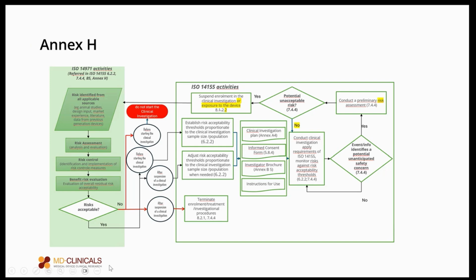It seemed that some confusion was that Annex H had possibly two or several rounds, where if something happens during the clinical investigation that is unanticipated, you need to go back to your risk management from 14971 and consider, and your second round kind of doesn't fit completely in our diagram anymore. So we now have two, and I hope the lines and the colors make it clear: before starting the clinical investigation and after suspension of a clinical investigation, where you have gone back to your 14971 activities again. So they may be different.